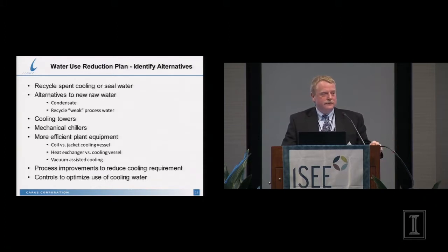Then there's cooling towers. You don't just have to use city water. There are mechanical chillers, and then there are more efficient plant equipment options. We're 100 years old - I wouldn't say all of our equipment is 100 years old, but some has been there for a long time. Some of the reactors with steam, with coils for heating or cooling, were designed when the cost of utilities wasn't an issue. So there are opportunities for more efficient heat exchange equipment, whether you switch from a coil to a jacket, or a cooling vessel to a heat exchanger, or even vacuum-assisted cooling. There are lots of technologies now that make sense, especially when you're measuring your utilities and can see the impact.